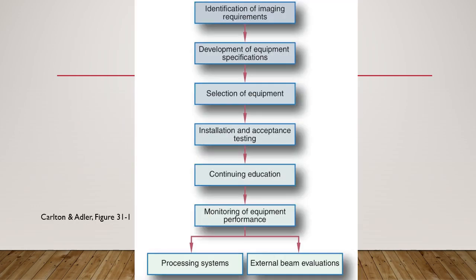When purchasing new equipment, we want to identify imaging requirements. Secondly, develop equipment specifications, select the equipment, then install and do the acceptance testing, which would be performed by the physicist, then do continuing education for the technologist, monitor the equipment performance, and then from there would be processing systems and external beam evaluations.